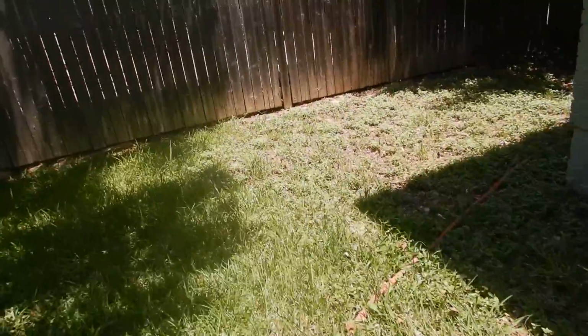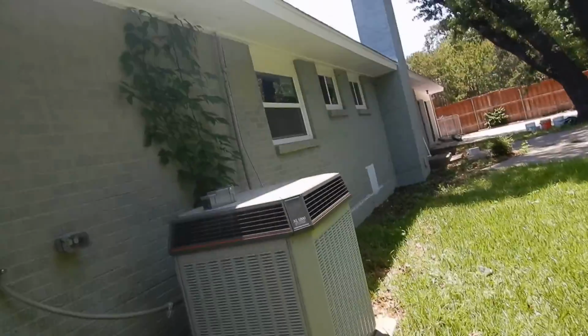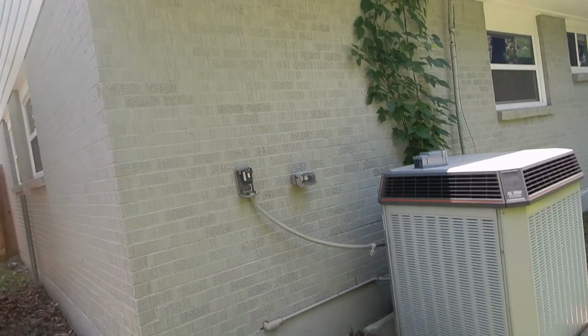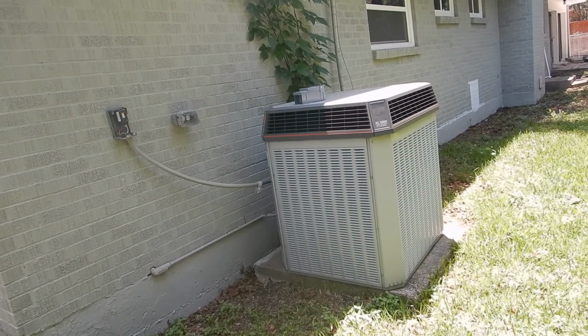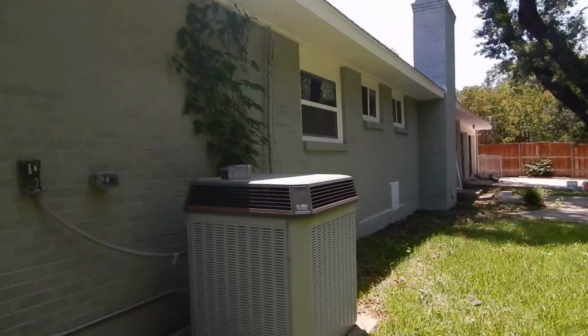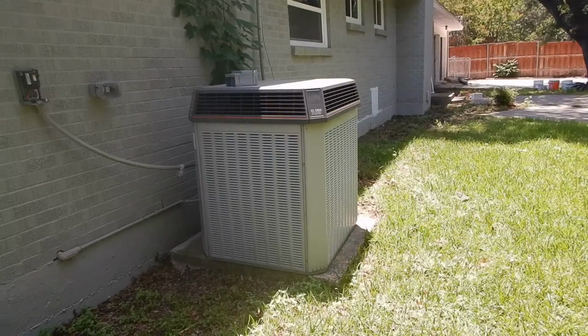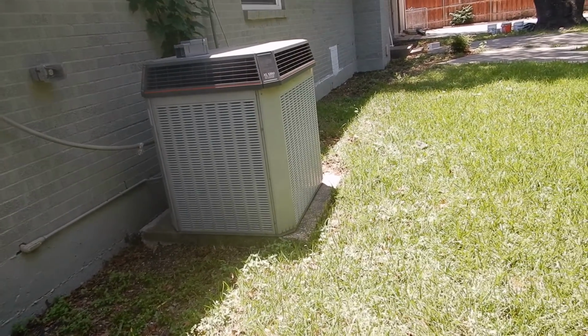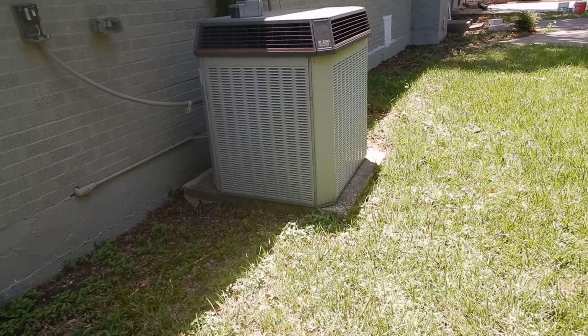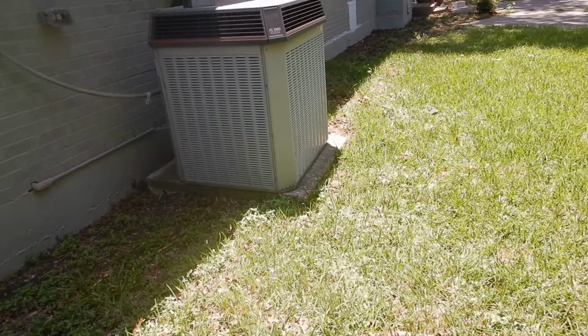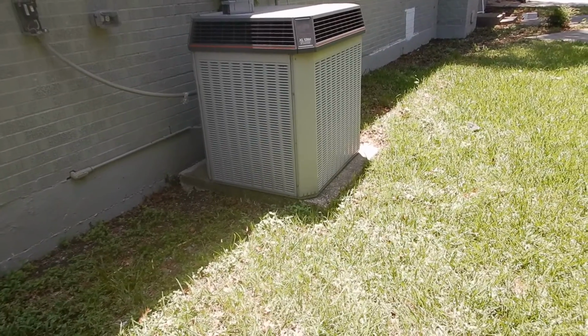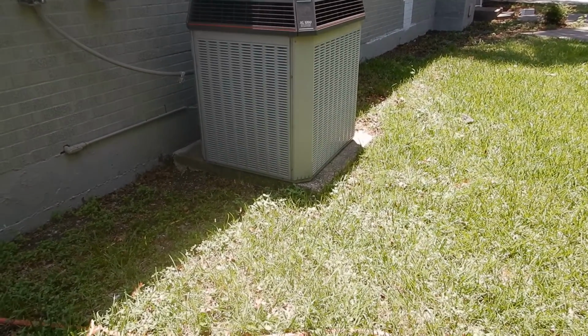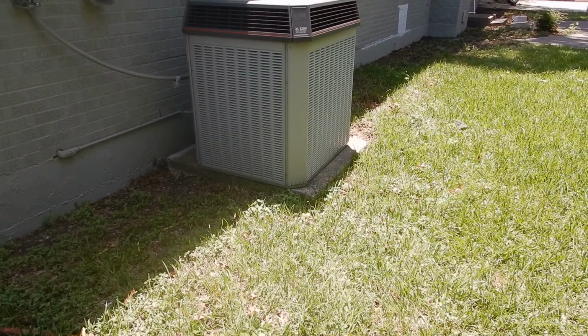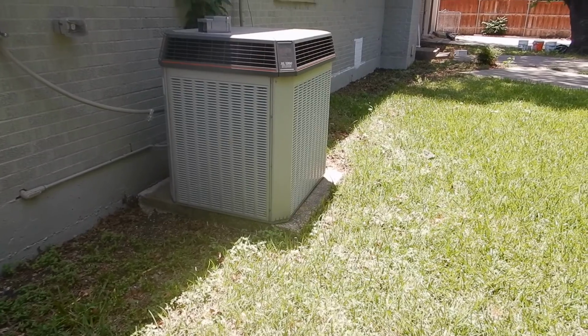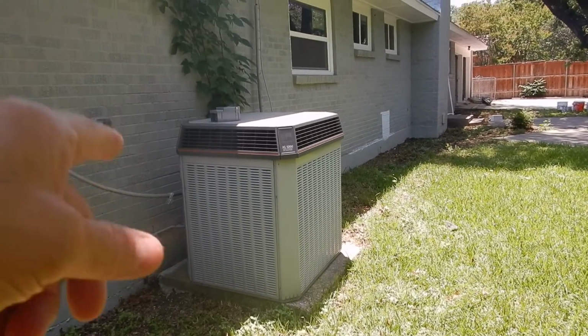Now here's this. According to the Texas Real Estate Commission: overfused, not level, no rain diverter, disconnect not sealed. Not according to the Texas Real Estate Commission: the missing insulation. They don't care how old a system is. They don't care what the refrigerant is. The homeowner might. According to the Texas Real Estate Commission, is it performing the function for which it's intended? Was it installed properly? Or is it a safety issue? So this unit was not installed properly.